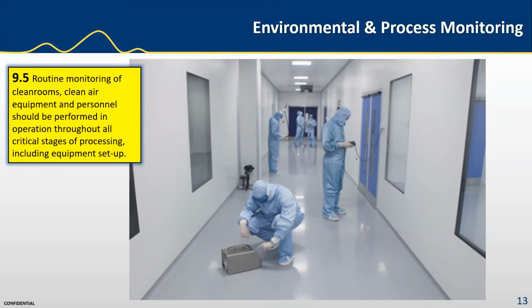So for the process monitoring, I would use trend analysis based on 1 cubic foot, 1 minute samples from your particle counters and using X out of Y events rather than following the certification classification particle concentrations based on a cubic meter. Some companies using a continuous monitoring system will use 1 CFM particle sensors and run for 36 minutes so they capture a cubic meter sample. Again, I would just make sure that you are capturing these events and monitoring an adequate volume of air. And if you need further information on that, you can definitely get back to me, and I can go deeper into that topic with this 9.5.